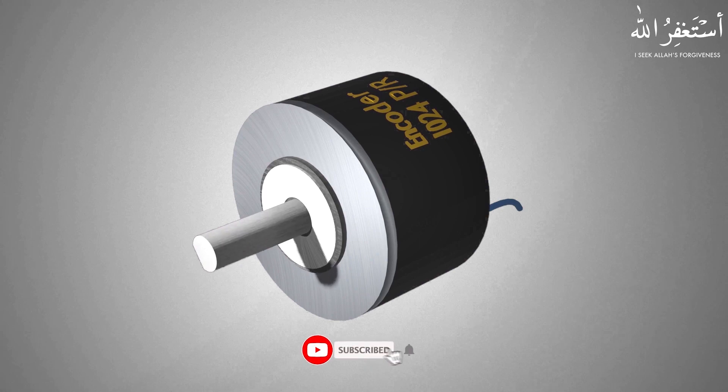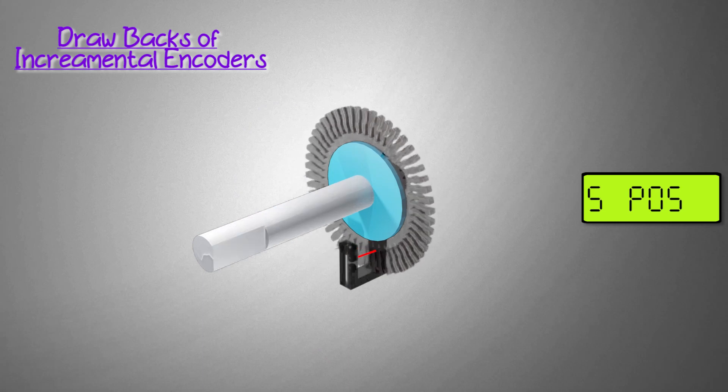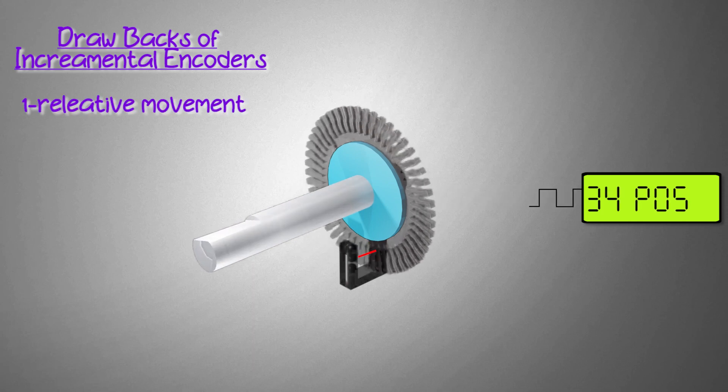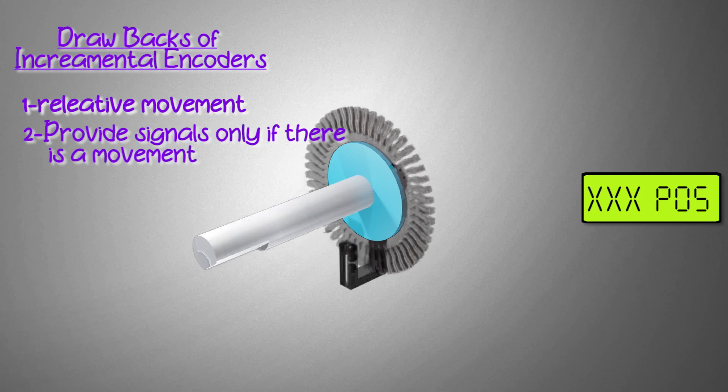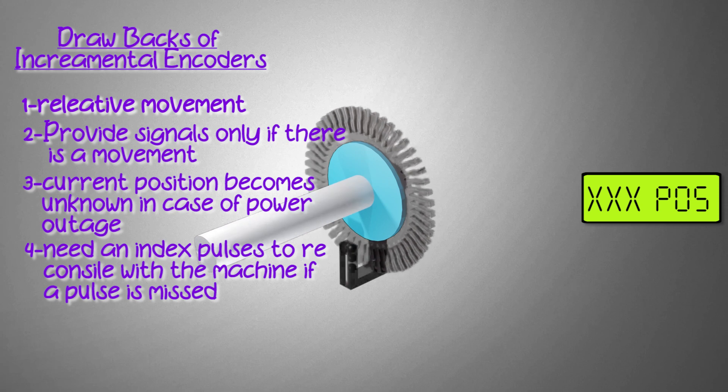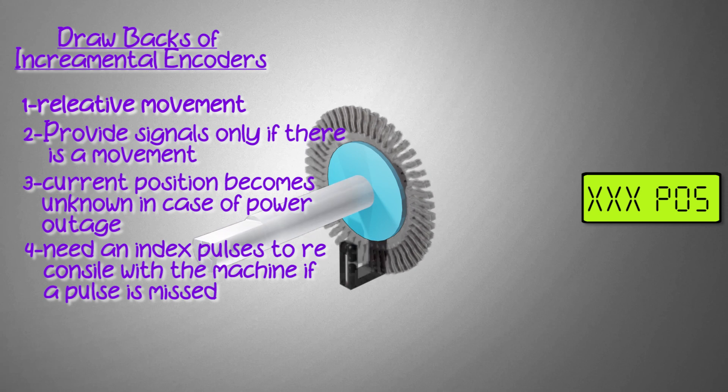Now while the information provided by the incremental encoder is incredibly useful, there are some drawbacks due to the fact that they only measure relative movement. They provide information if there is movement, and if there is a power loss for whatever reason, the current position becomes unknown. They also require constant monitoring. If there is noise in the system or the encoder pulse is missed, then we have to reset the encoder reading to reconcile with the machine operation using an index pulse.